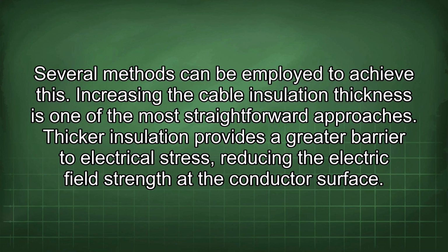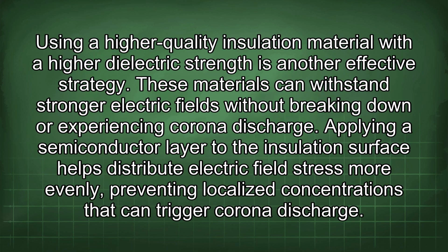Increasing the cable insulation thickness is one of the most straightforward approaches. Thicker insulation provides a greater barrier to electrical stress, reducing the electric field strength at the conductor surface. Using a high-quality insulation material with a higher dielectric strength is another effective strategy. These materials can withstand stronger electric fields without breaking down or experiencing corona discharge. Applying a semiconductor layer to the insulation surface helps distribute electric field stress more evenly, preventing localized concentrations that can trigger corona discharge.